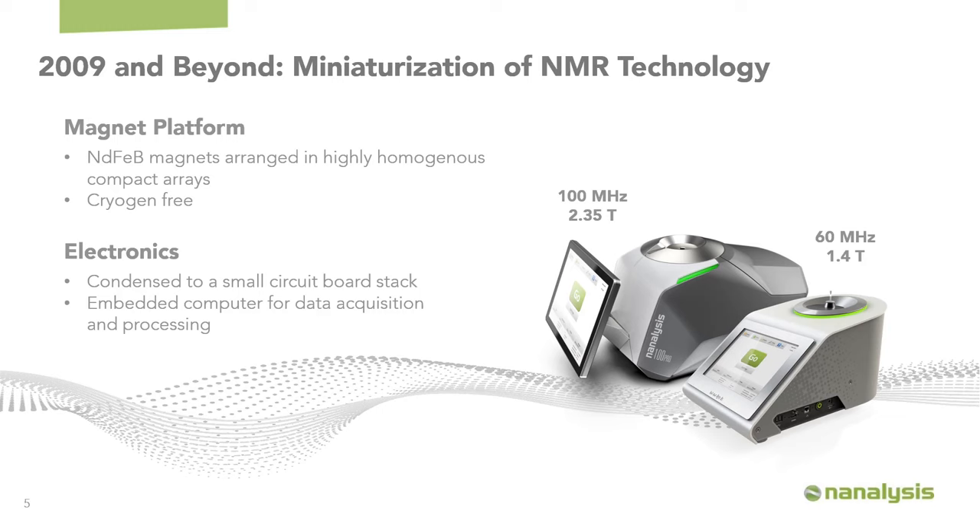The miniaturization of benchtop NMR spectrometers by Nanalysis was achieved first by using rare earth permanent magnets — specifically neodymium iron boron — compiled in a highly homogenous compact array with very limited stray field, so the instruments are very safe to be around and use the minimal amount of magnetic material required with almost no current draw. This makes them cryogen-free, effectively maintenance-free instruments.